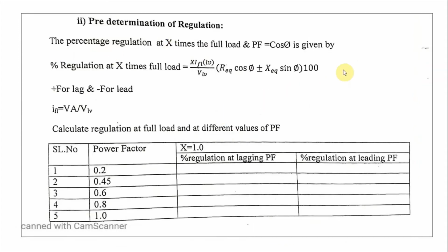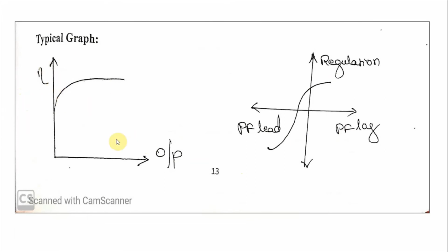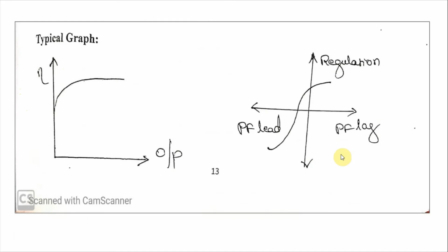Similarly, the regulation is calculated using this expression. So here we will keep the loading condition constant and we'll calculate the regulation for different power factors, both leading as well as lagging. So this is the typical graph. We expect the efficiency versus output graph to be something like this, similar to this pattern, and the regulation graph will be somewhat similar to this. Small variation can be expected because of the practical situation.